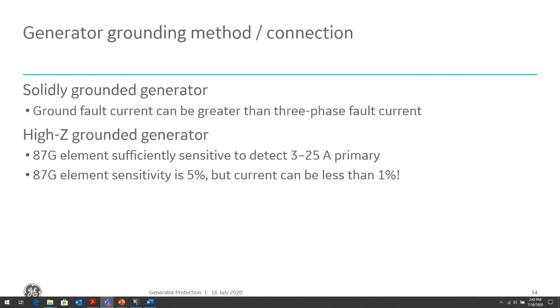If you want to protect a generator properly from ground fault currents, you want to use a high Z grounded generator system. However, the protection package becomes more costly because there are more different types of protection that you will need. Whereas with the solidly grounded generator, all you basically need is a ground overcurrent relay and you're protected. Whereas in the high impedance, there are lots of various different types of protection elements you'll need.